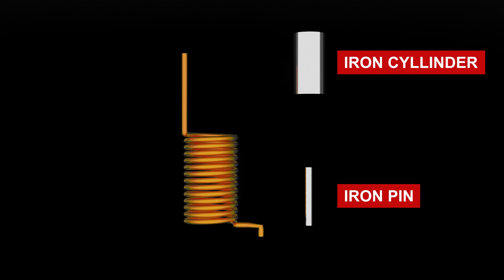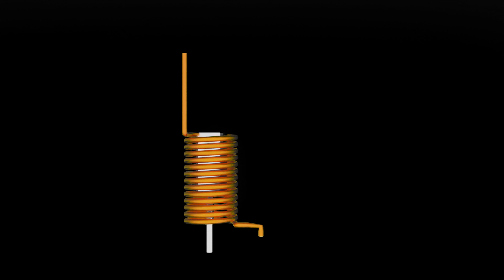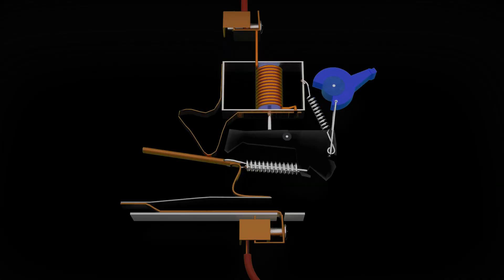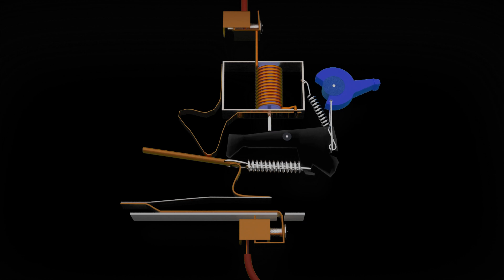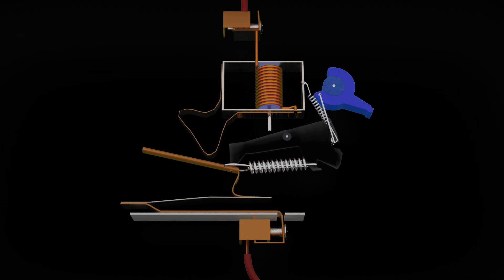This coil consists of an iron cylinder and a pin. Due to the electromagnetic force generated in the coil, the iron cylinder exerts a force on the pin below, and the pin hits the trigger—that is, a little force is applied to the trigger. This causes the trigger to move the lower contact plates from its previous position, and through the trigger mechanism, the circuit breaks.